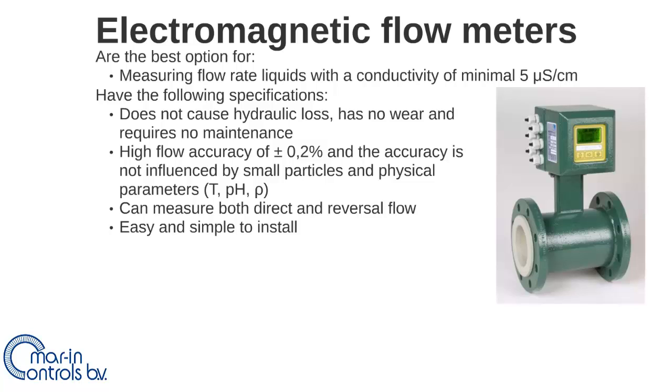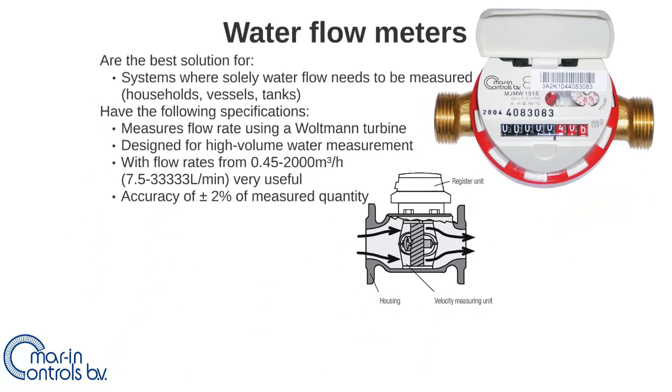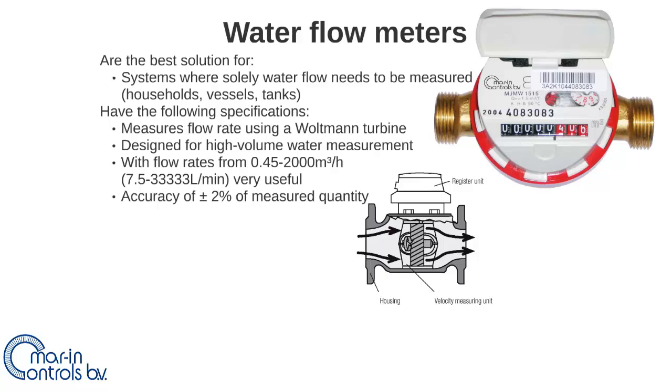The electromagnetic flow meter can measure both direct and reversal flow and is easy and simple to install. The water flow meters are the best solution for systems where solely water needs to be measured in large volumes, operating at high flow rates using a Woltmann turbine. This is a cost-effective way to measure water, and measuring with a mechanical counter results in an accuracy of approximately 2%.